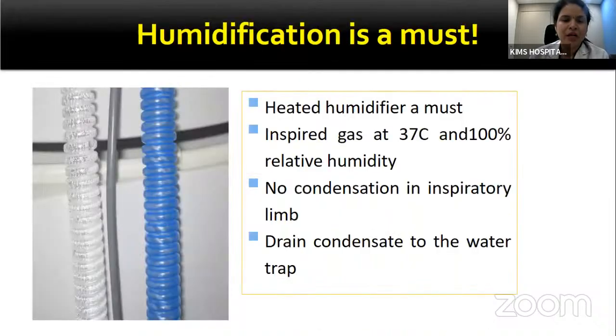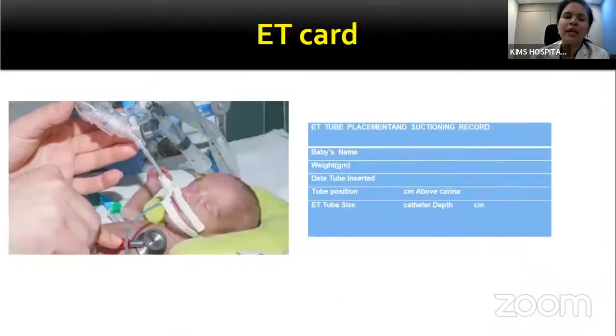Ventilation can actually be harmful if appropriate humidification is not being performed, and this is possible by a servo-controlled heater humidifier, which allows the delivery of inspiratory gases at 37 degrees Celsius and 100% relative humidity, and no condensation is to be seen in the inspiratory limb, and any condensate in the expiratory limb must be immediately drained.